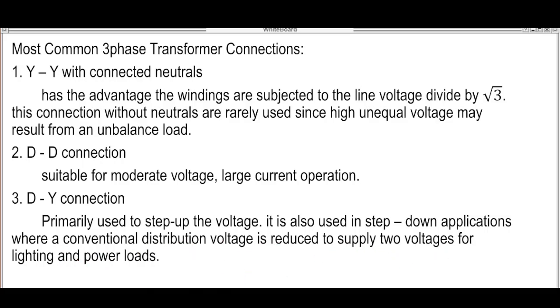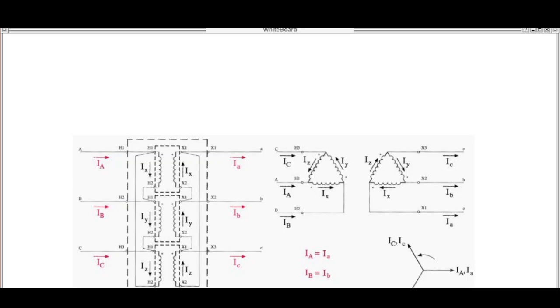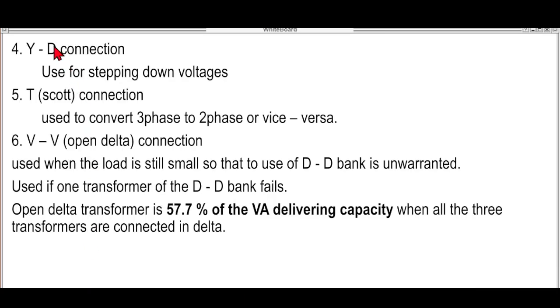So, for example, delta then Y. When Y is the secondary, we could get two types of voltages. We have line-to-line at 240, while our line-to-neutral is 120. Then the Y-to-delta or delta-to-Y connection is used for stepping down voltage. T-Scott is used to convert three-phase supply to two-phase or vice versa.